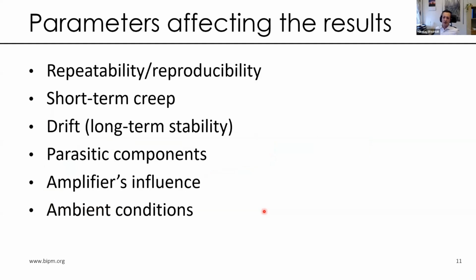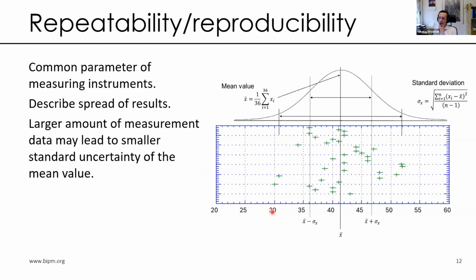So the main part of our talk is to actually talk about parameters that affect the results. We grouped these parameters in six points. That's repeatability or reproducibility, short-term creep, drift, parasitic components, the influence of the amplifier, and ambient conditions. When we talk about repeatability or reproducibility, this is mainly the common parameter of all measuring instruments. So when we measure the same quantity in the same or similar measurement conditions, the measuring instrument gives us slightly different values. And these two parameters describe the spread of the results. In other words, measurement precision.